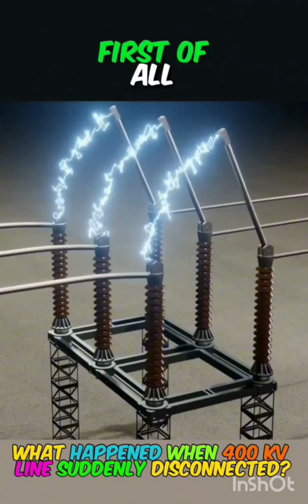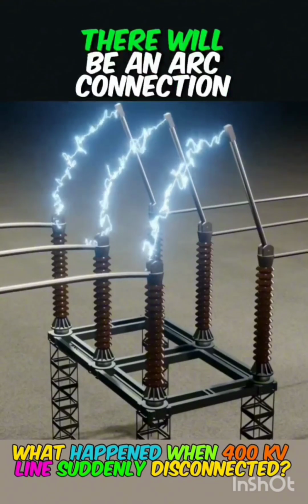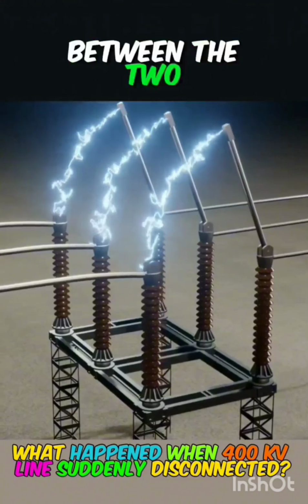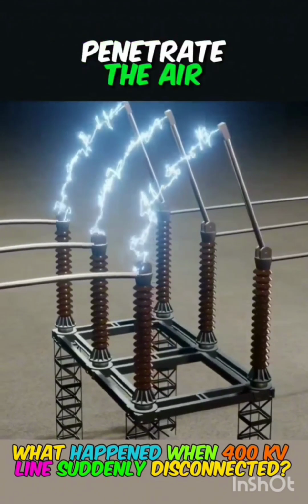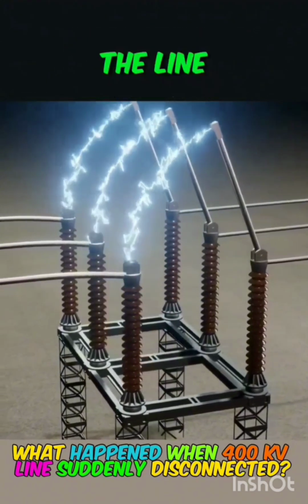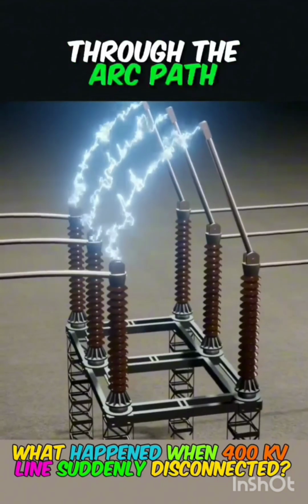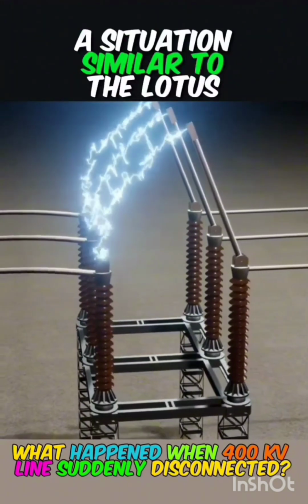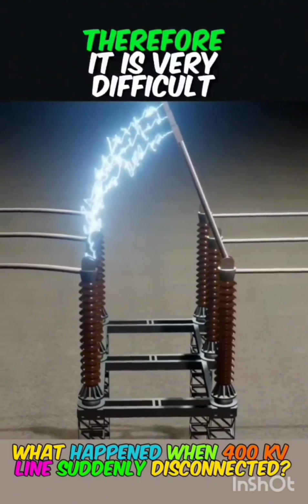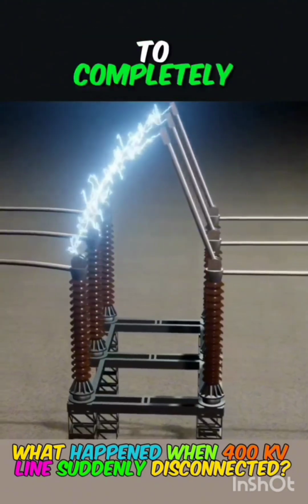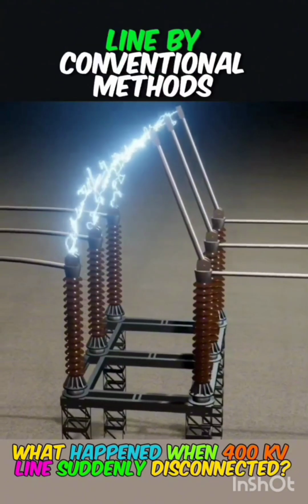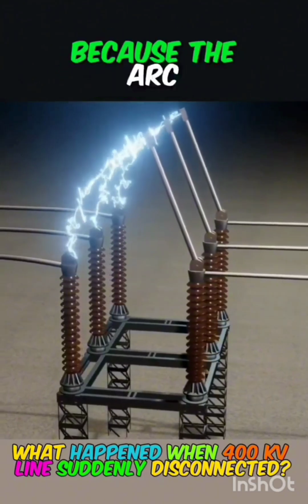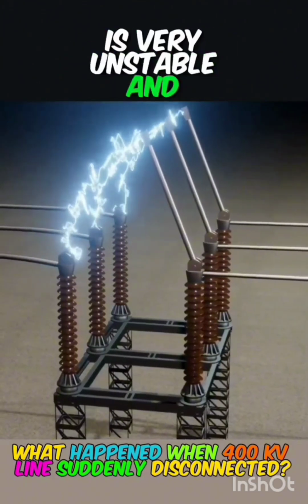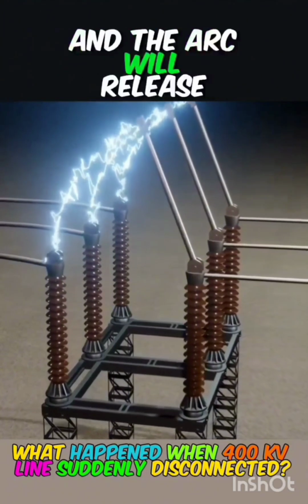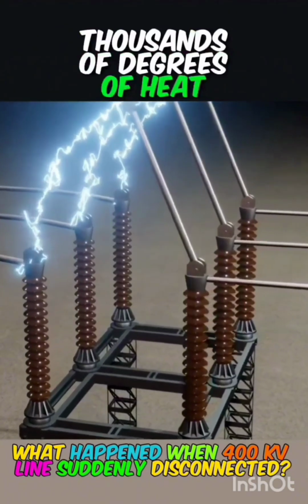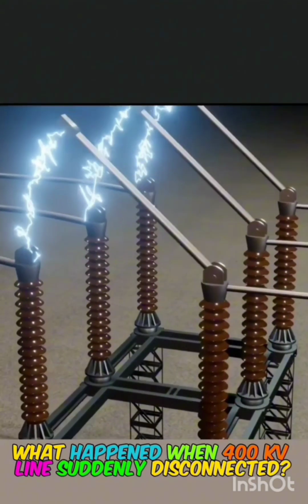First of all, at the moment of disconnection, there will be an arc connection between the two contact ends that can penetrate the air, which means that the current in the line can still be connected through the arc path, a situation similar to the Lotus root break. Therefore, it is very difficult to completely disconnect a high-voltage line by conventional methods because the arc is very unstable and difficult to extinguish, and the arc will release thousands of degrees of heat, enough to melt the two ends of the contact and damage it.